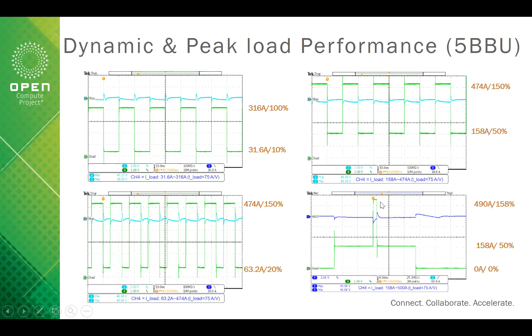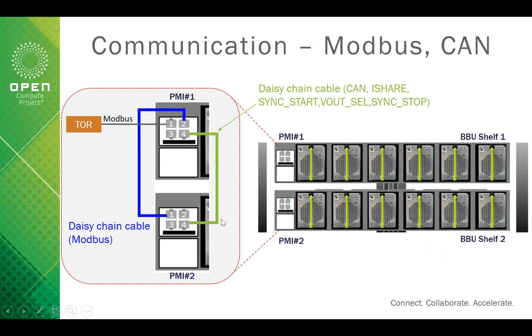If we want to have more power output, we have 2 BBU shelves in parallel. Then we have 12 BBU, 2 BBU shelves, 2 PMI, and 1 TOR switch, and we utilize 2 daisy chain cables to do the communication. One daisy chain cable is for the Modbus, the other one is for the CAN bus. The Modbus is mainly for communication with the TOR switch, to report the BBU information to the TOR switch and also receive some commands from the TOR. Then we can change the discharge time, change the charge current, or also do the firmware upgrade.